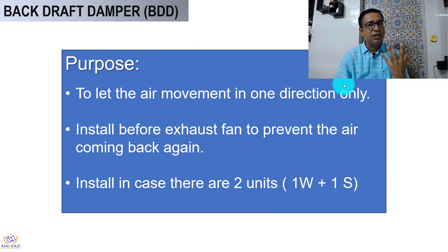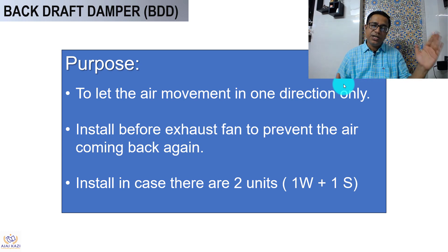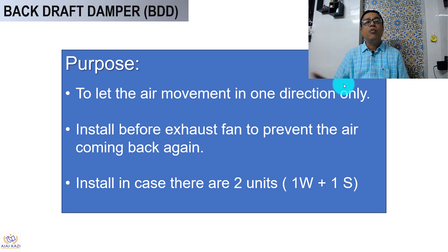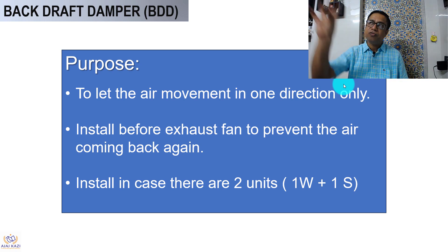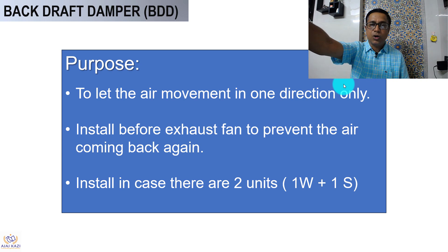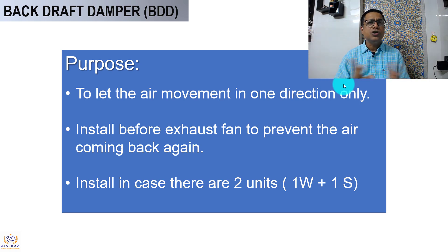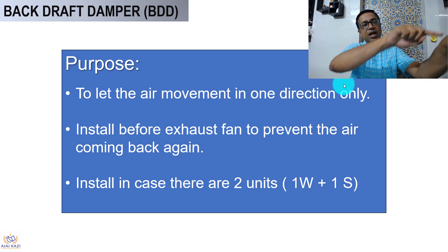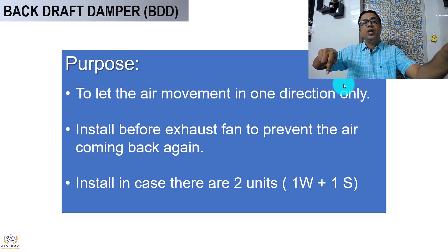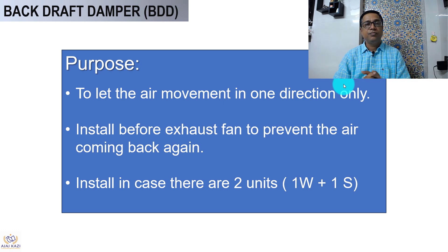Now let us look at another damper called the Back Draft Damper, or BDD. The purpose is to allow air movement only in one direction. They are installed before exhaust fans to prevent air from coming back. They are also installed when you have two units — one working and one on standby — so air from the working unit does not flow back into the standby unit. BDD prevents that.